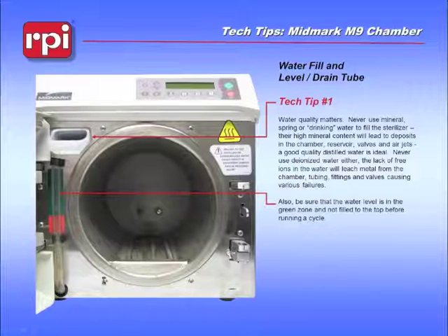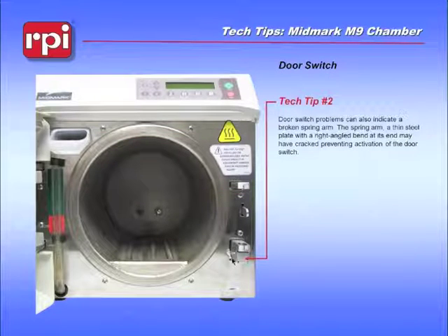We have a door switch that actually tells the machine when the door has been closed and sealed. And built into the switch assembly is a piece of spring steel that has a slight bend on the end of it. If that spring steel breaks, you'll get intermittent failures on your door switch. If replacing the door switch doesn't solve your problems, take a look at that piece of steel and make sure that that right angle bend is still in place.